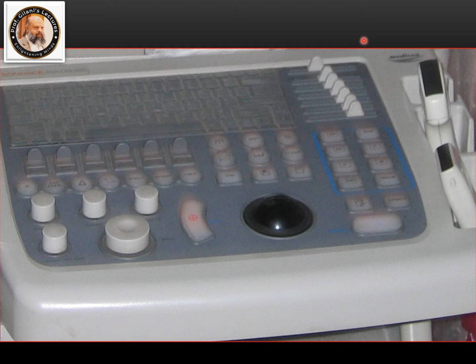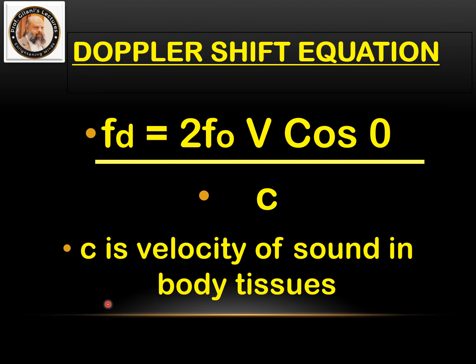The Doppler principle says that when sound is reflected from a moving object, the frequency of the reflected waves is different from the frequency of the incident waves. This is the Doppler shift equation which is used: Fd is equal to 2 Fo V cos theta divided by C. Fd is the Doppler shifted frequency, what we measure. V is the velocity of RBCs, what we want to know. Fo is the transducer frequency. Cos theta is the cosine of the angle of the ultrasound beam. C is the velocity of sound in body tissues.